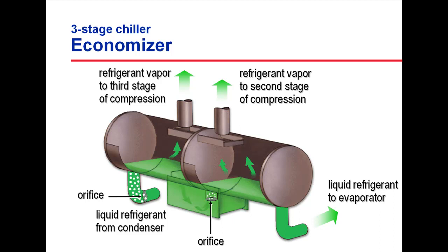Liquid refrigerant from the condenser enters the first orifice expansion device, which reduces the pressure of the refrigerant to that of the third stage impeller inlet. This pressure drop causes a portion of the liquid refrigerant to flash, and the resulting mixture of liquid and vapor enters the high-pressure chamber of the economizer.